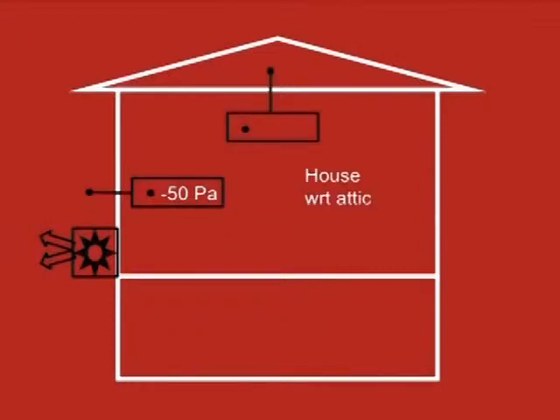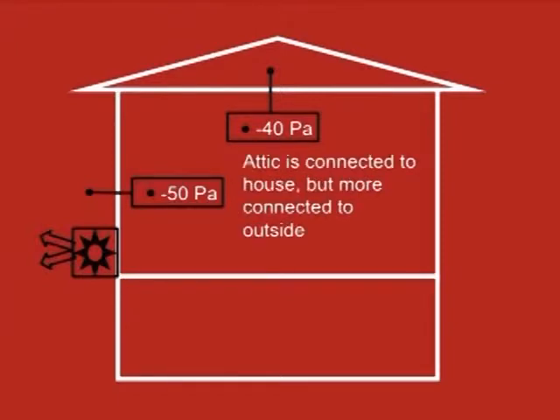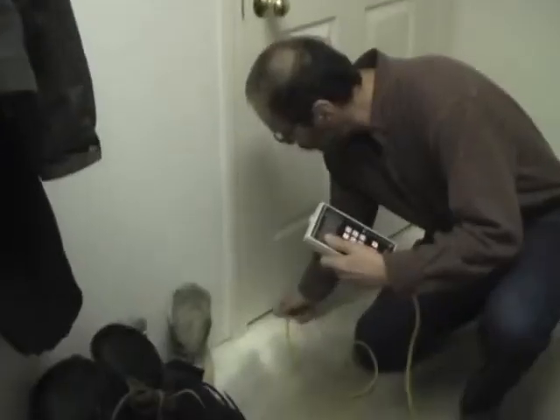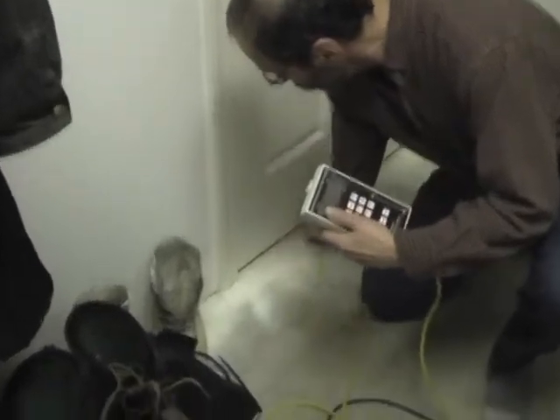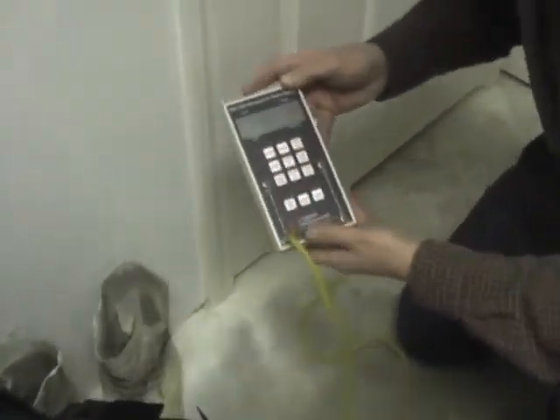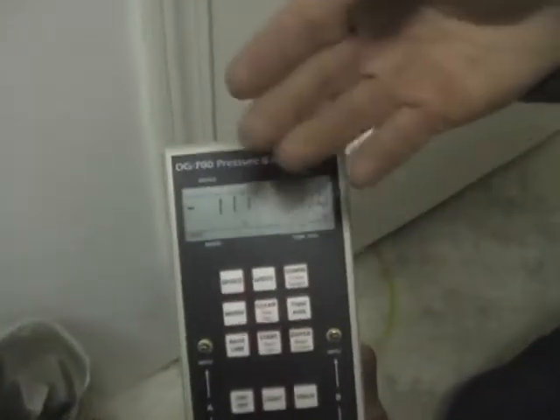If we measure the house with reference to the attic and record a value of minus 40 pascals, we can say that the attic is connected to both the house and the outside, but it is more connected to the outside. This type of information is important for developing a weatherization or retrofit strategy for a building.